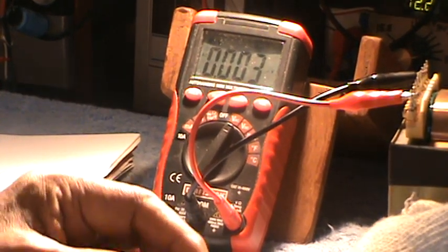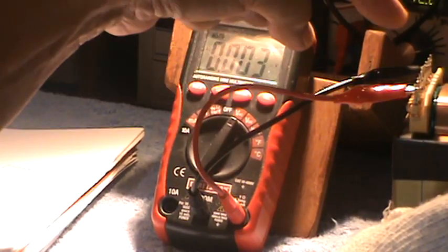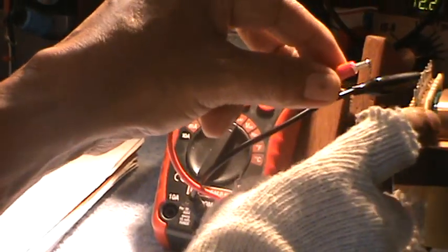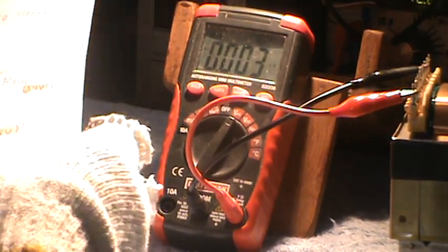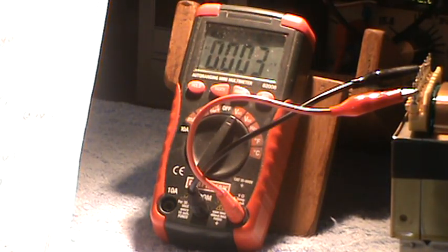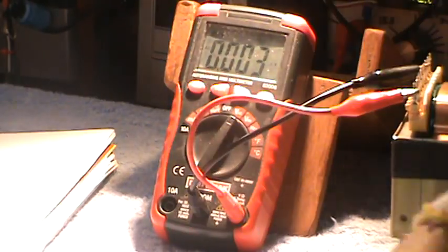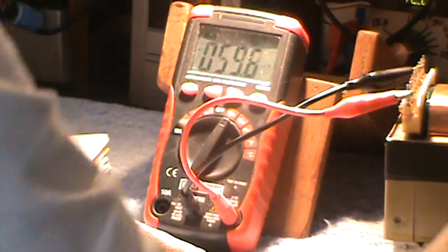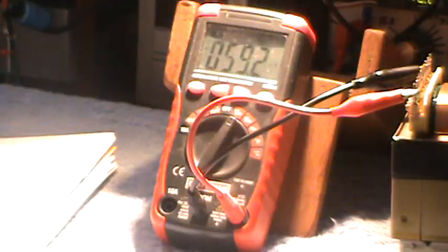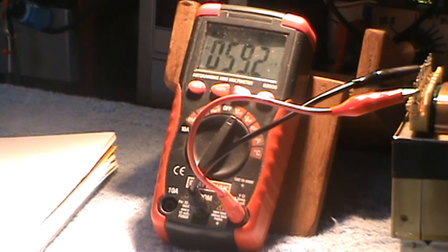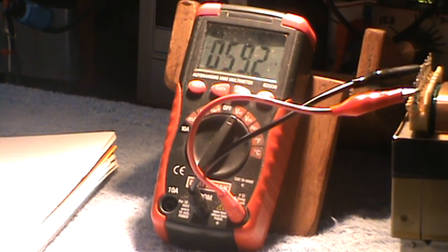I will try to remove this one again. Then I will go with 3 and 10. First terminal is on 3. Terminal number 10 is the last one here. Because there is a resistance reading between terminals 3 and 10 of 15.6. And let us measure the voltage across terminals 3 and 10. Across terminals 3 and 10, the voltage is 59.2. Could you see it, guys? Yeah, it's 59.2 volts. That's alternating AC voltage.